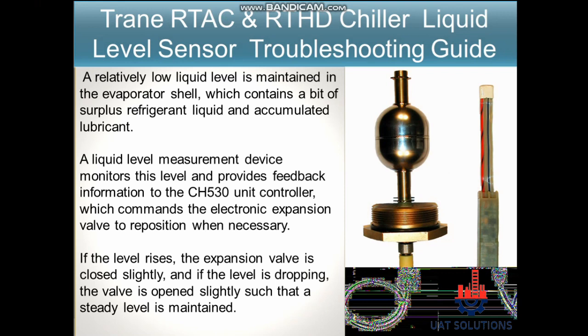If the level rises, the expansion valve is closed slightly, and if the level is dropping, the valve is opened slightly, such that a steady level is maintained.